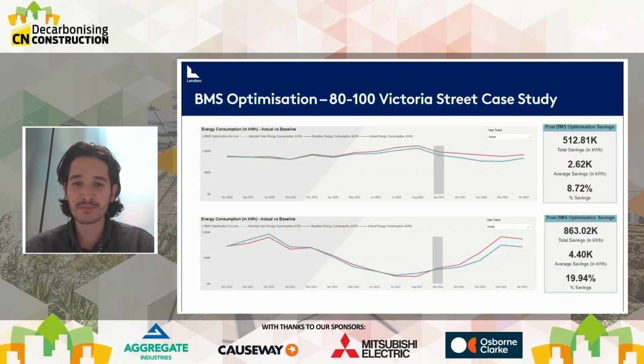So the review has helped uncover opportunities that would, in some cases, save some of our buildings around 15% of total energy. Several opportunities for control improvements were identified and implemented, including a control strategy to allow our air handling units to vary supply air temperature based on demand rather than outside air temperature, enabling fan coil units on tenanted floors to operate much more efficiently zone by zone, reducing occurrences of simultaneous heating and cooling, which we frequently observed.